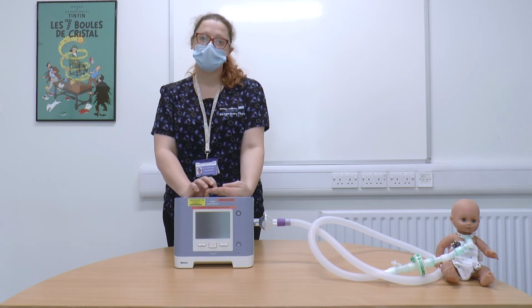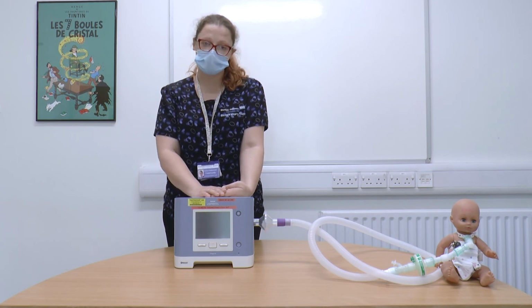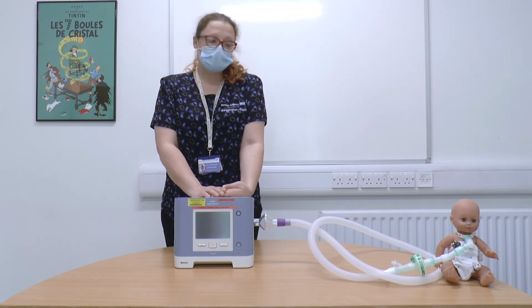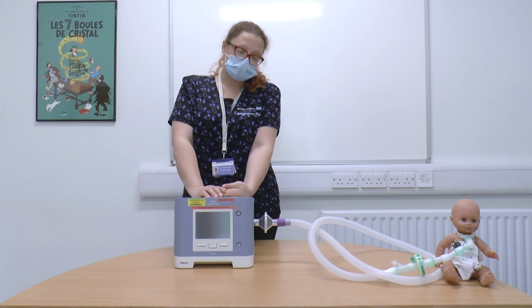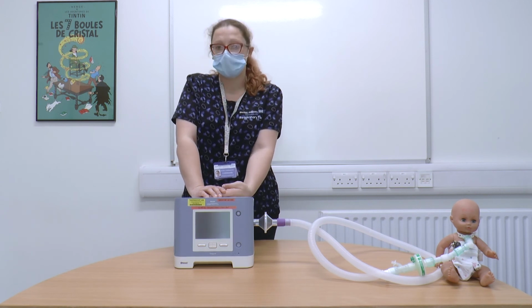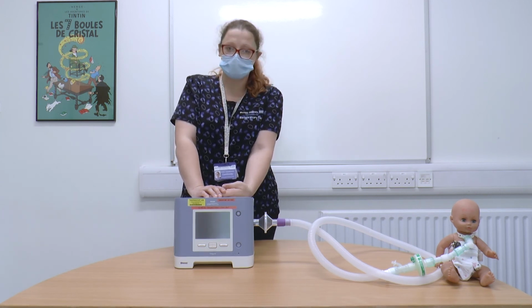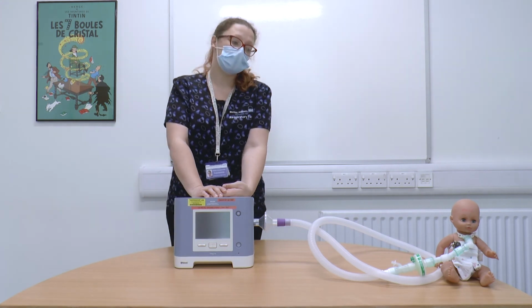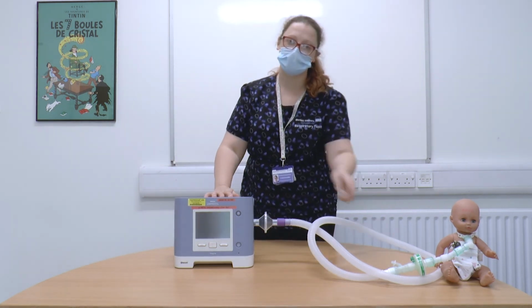All of those mean that it thinks the child may have a blocked tracheostomy or no flow is getting to the child. It may be that the exhalation port is covered, it may be that your child needs suction, it may be if you're on a wet circuit you have got humidity water building up in the tubing, or it may be that you have a saturated HME.